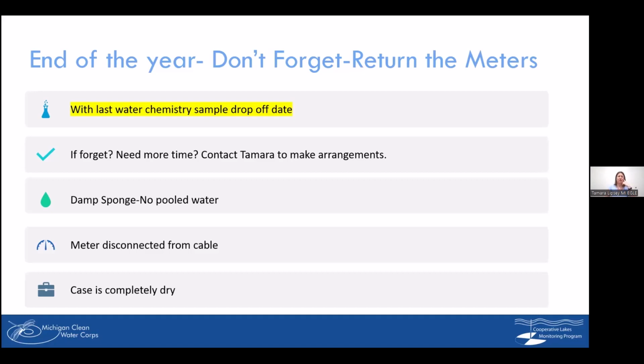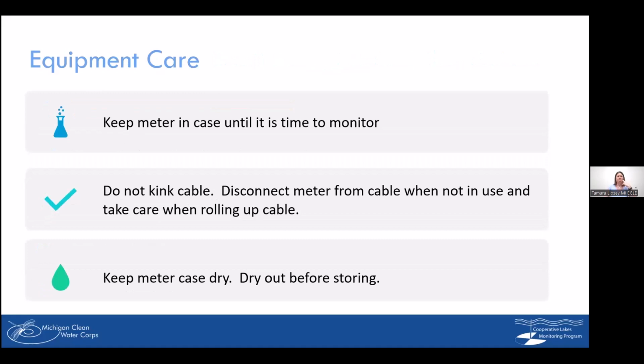I opened one case this year and it was just full of mold, which didn't ruin the meter. It just discolored it in some ways, but it was a good prompt for me this year to remind everyone to dry out your meter and then shut the case. But do keep your meter in the case until it's time to monitor. I have had one meter come back where the screen's a little pixelated in one area, and I think it's because something got sat on top of it. So just keep it in the case until it's time to do your monitoring. Don't kink that cable and disconnect the meter. And also take care when you're rolling up the cable. And then keep your meter case dry.